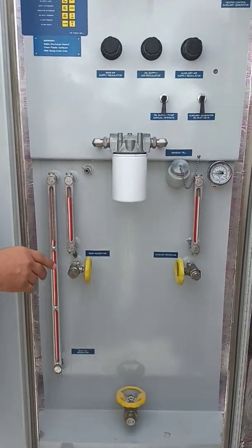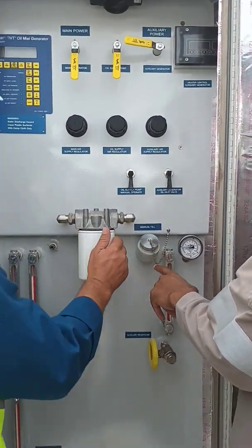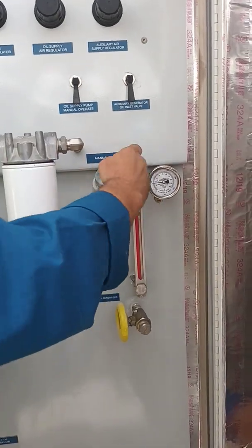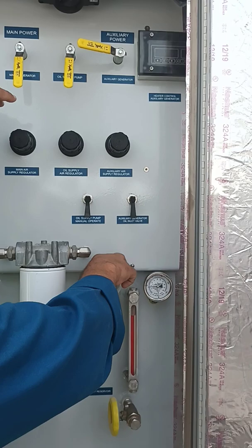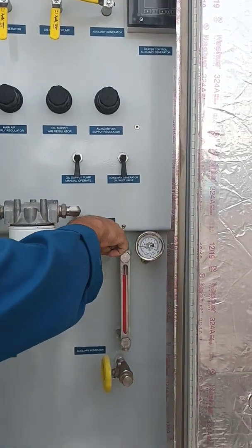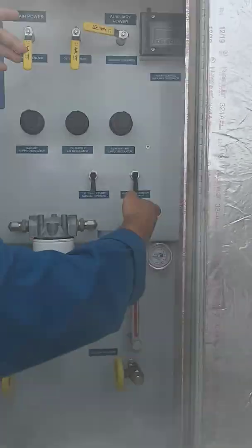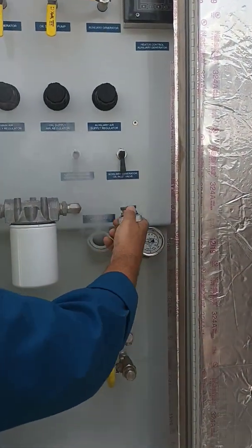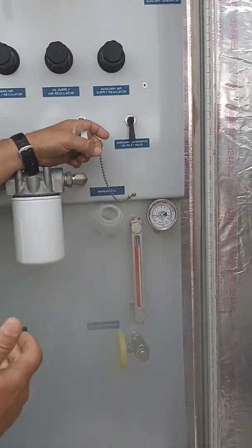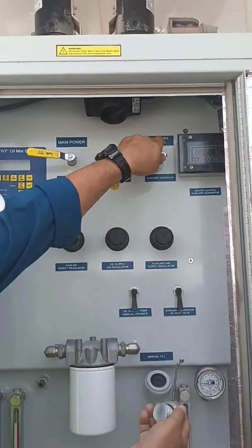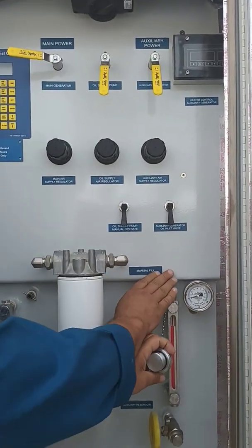If we do a calibration on the system, we use this connection. And fill it from here, huh? Yeah, to fill from here, you see. A lot of people make the mistake, but it's not going to kill you because it's only 50 millibar. So you can open now. Yeah, that's what I told you, keep away. You cannot put oil in now because you get the oil mist blowing out. So you need to close it. You run your auxiliary. You see the valve closed. Now you can feel, there is no pressure anymore.